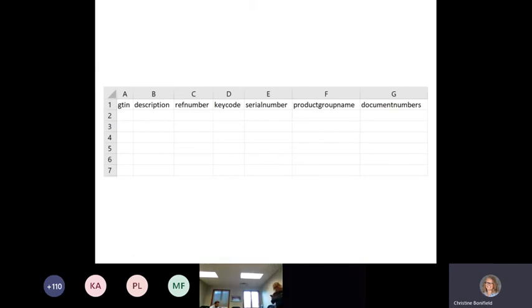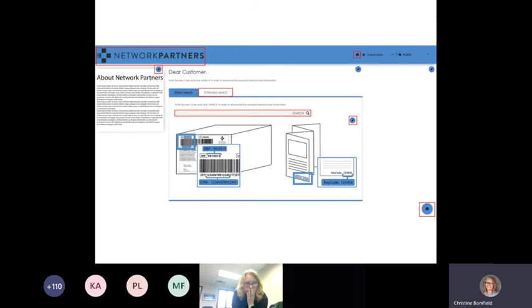You can link these SKUs to an eIFU or multiple eIFUs. You can link the SKU to a country language specific file, or you can configure the system to display a particular language based on the user's location or their language preference. You can even let a user from Lithuania know that the eIFU they are looking for is not available in their language because the SKUs associated with that eIFU are not registered for sale in Lithuania.